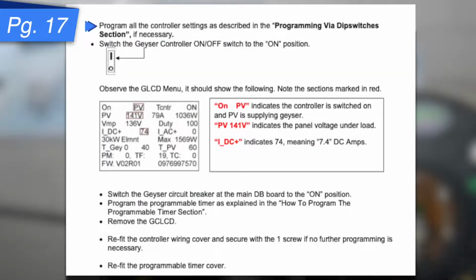All right, moving over to page 17. Now you're going to program all the settings as described in the section before. So if the default settings are incorrect, you are now going to need to go through the dip switches and set that up. Once you are ready to do this, you can now switch the geyser controller, the toggle switch at the bottom of the controller, into the on position. And straight away, what do I want you to do? Look at the GLCD screen. That little multi-tool we've plugged in, and this is what you should be seeing.